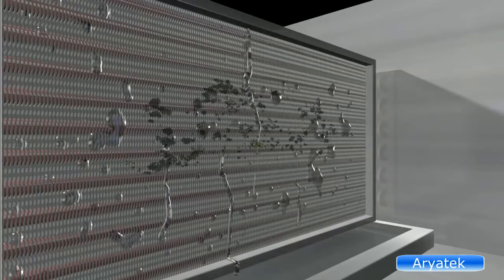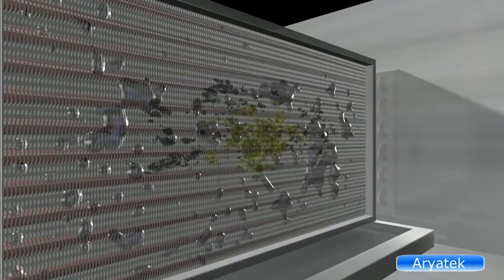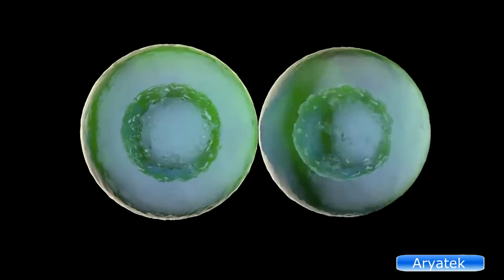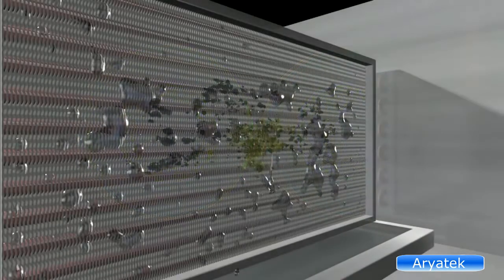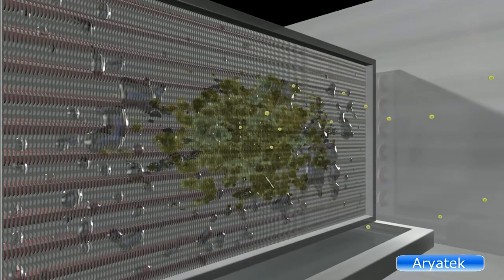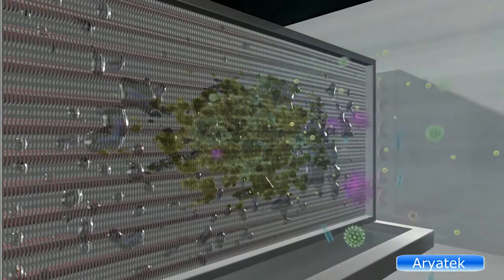We now know that as soon as the condensate is produced, mold and biofilm start growing. Mold takes 4 to 6 hours to double, so it can easily multiply into a billion organisms in 12 days. As long as it's alive, it will cling to the coil fin. Its sticky surface attracts and grips the dirt, forming the biofilm.